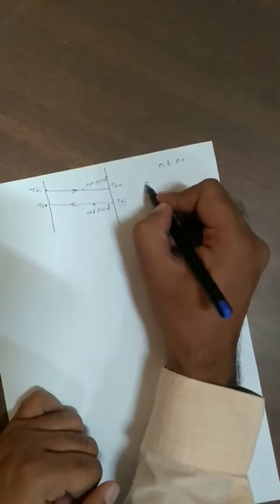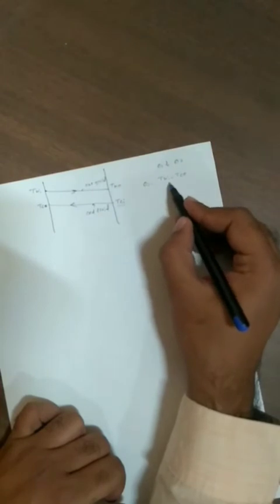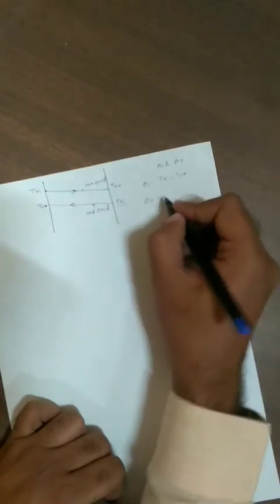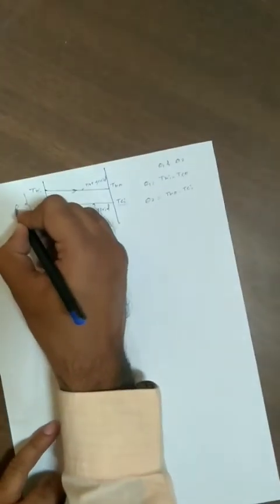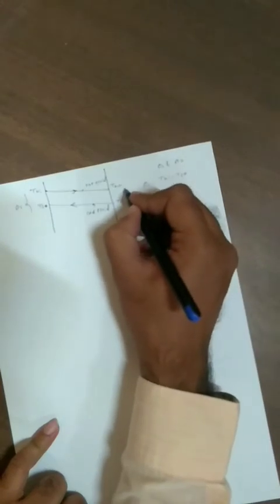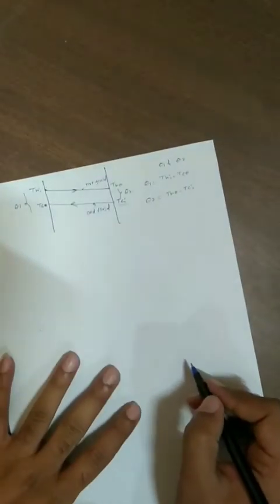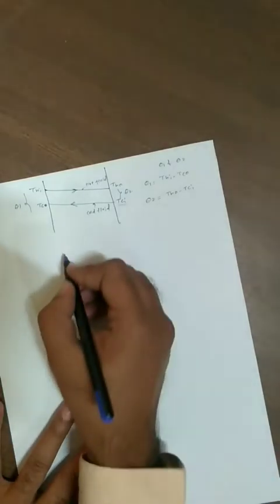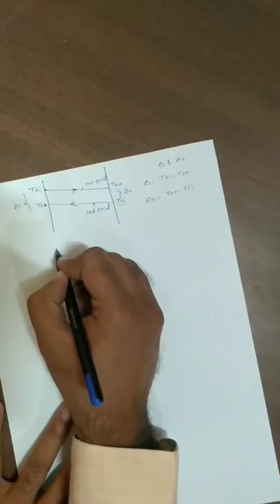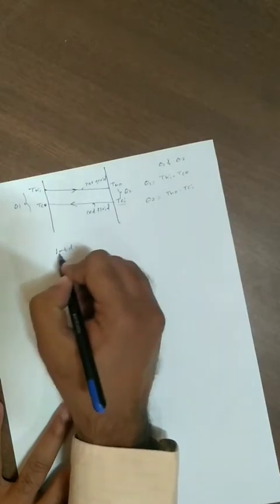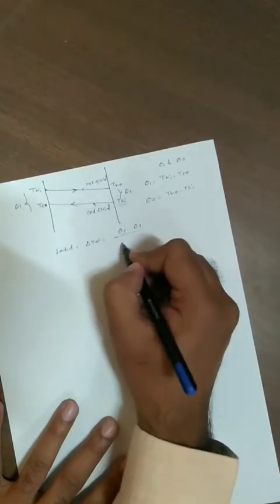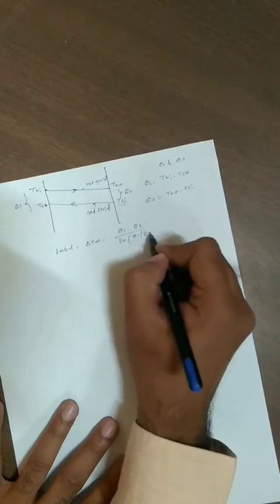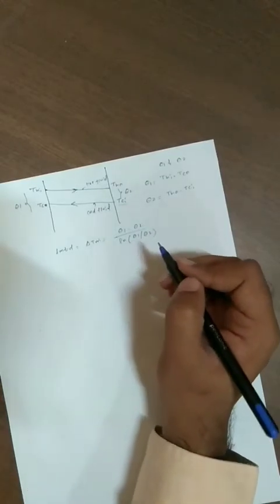Okay, so for this, theta 1 is equal to THI minus TCO, while theta 2 is equal to THO minus TCI. So the difference between these two is named theta 1, and the difference between these two is named theta 2. Therefore LMTD, which is equal to delta Tm, is equal to theta 1 minus theta 2 divided by ln of theta 1 by theta 2. So we are going to place the values in it.